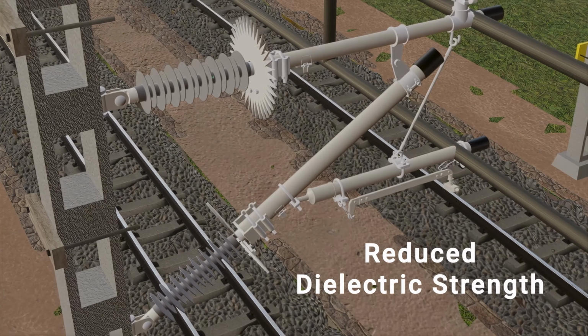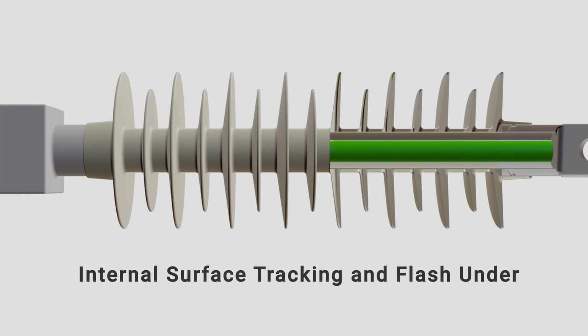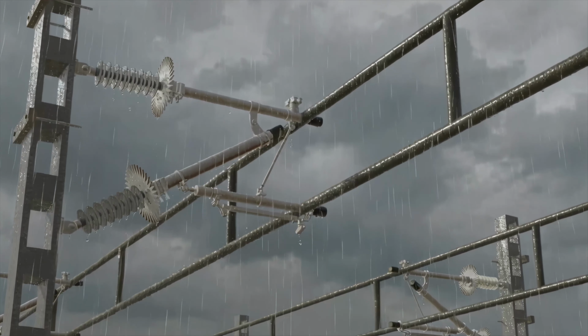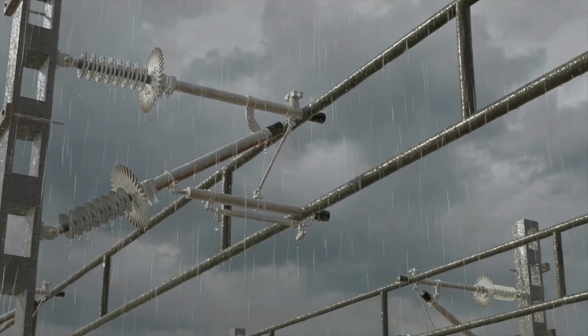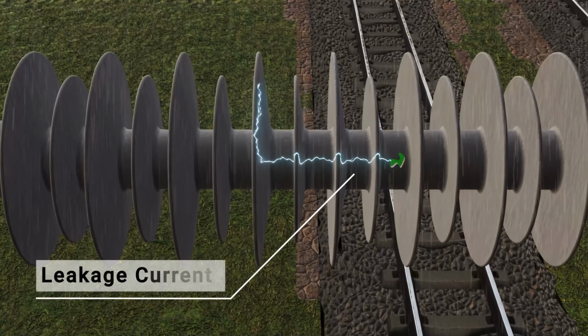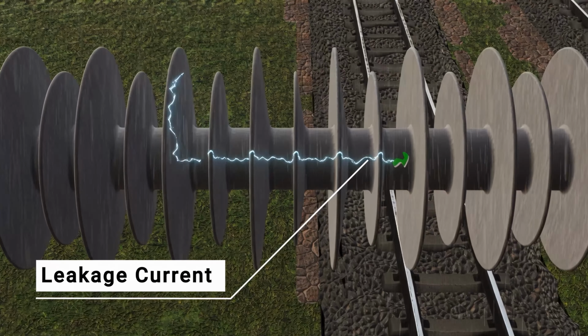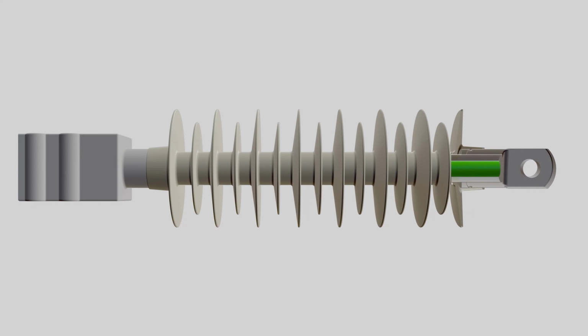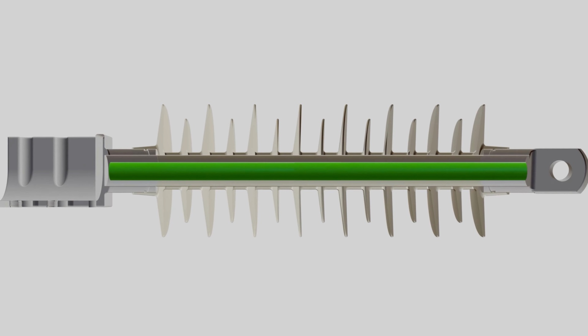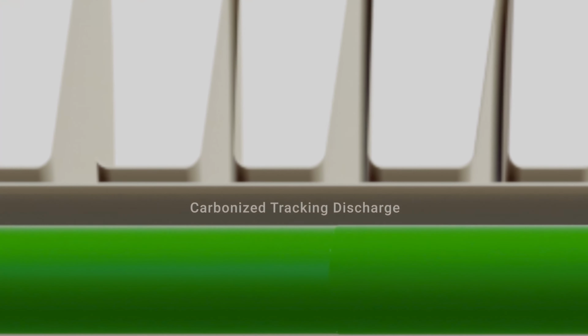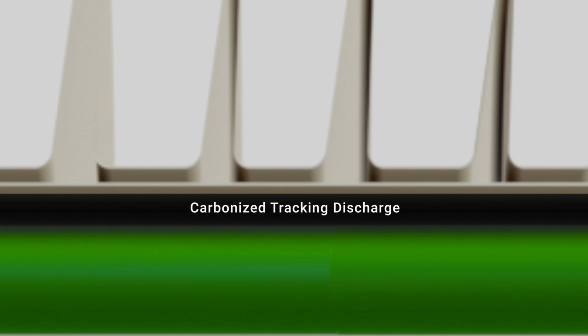Third, internal surface tracking and flashover. Moisture creates conductive paths along internal interfaces. This promotes leakage current and partial discharge activity. Over time, this can result in flashover, an internal carbonized tracking discharge along the interface between the core rod and the housing.